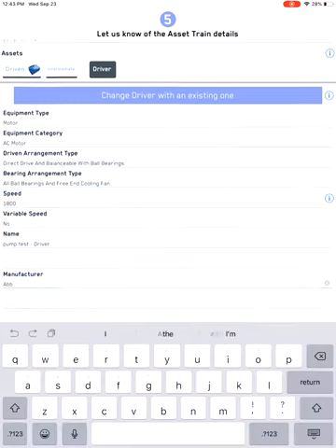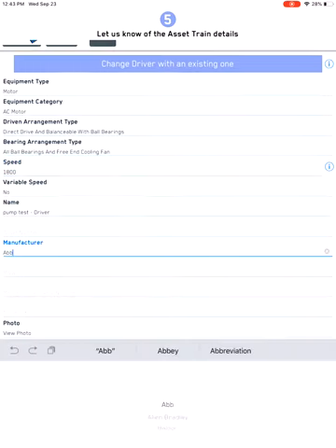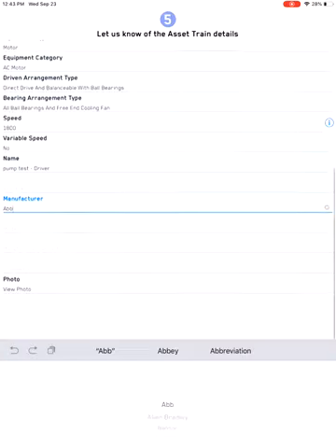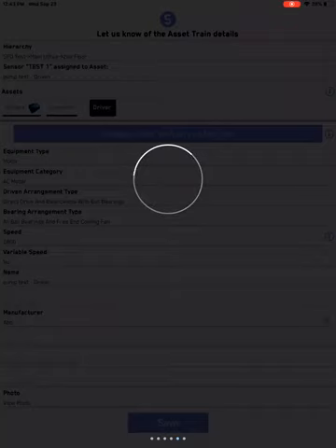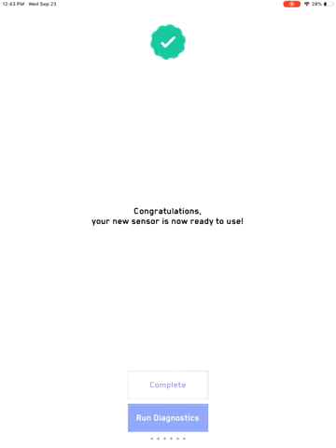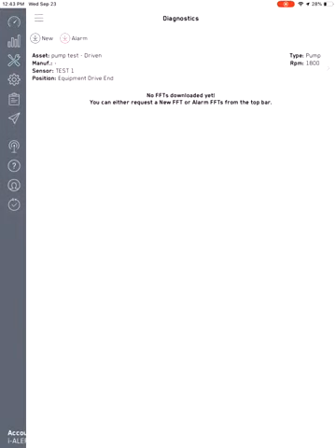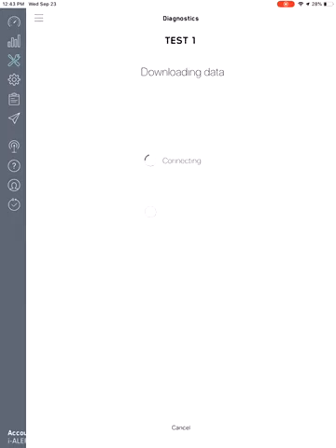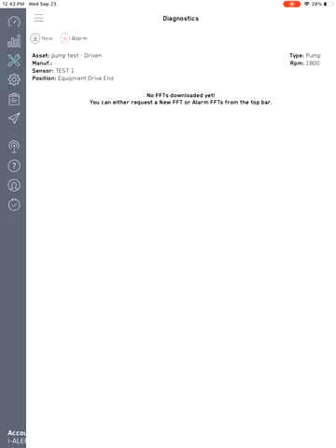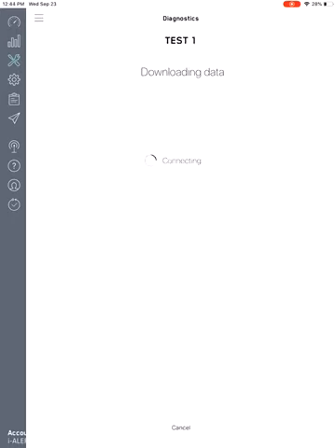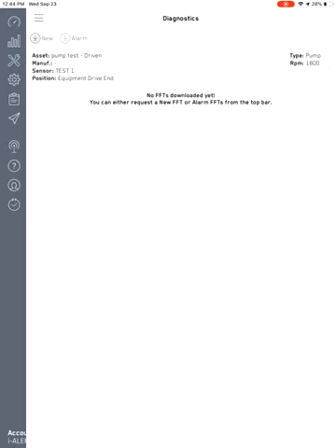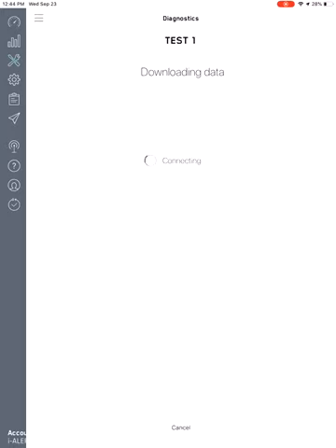And then after that, once I have everything, all the major information filled out, I click save. And once I click save, I'm pretty much ready to go and run my diagnostics. But like I said in the beginning, you have to fill out the mandatory information, but to get the most optimized results, the most accurate results, you would have to put all the other information. So once you're complete, you can go to the diagnostics page and you can request a new FFT spectrum by downloading a new spectrum right there, or you can download all the alarm spectrums as well. So for right now, let's just download a new spectrum and run diagnostics against it.